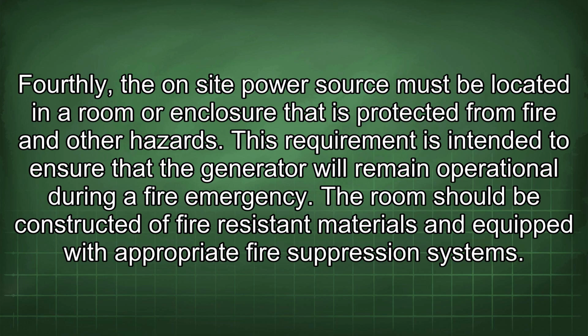Fourthly, the on-site power source must be located in a room or enclosure that is protected from fire and other hazards. This requirement is intended to ensure that the generator will remain operational during a fire emergency. The room should be constructed of fire-resistant materials and equipped with appropriate fire suppression systems.